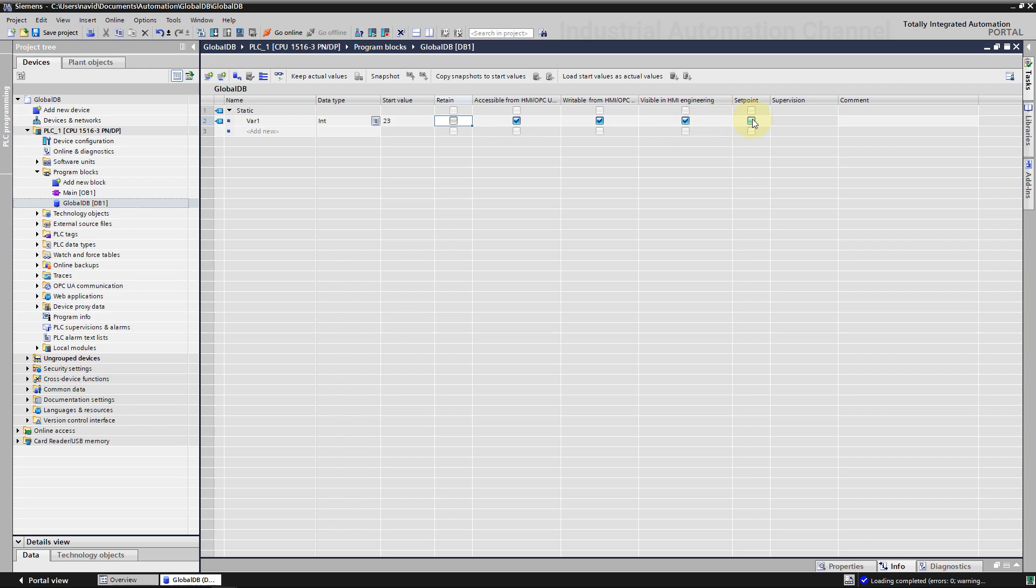Next, we can mark tags as set point. During commissioning, these tags can be initialized online and we don't need to set the CPU to stop mode. It can remain in run. In addition, the current tag values can be transferred as start values to the offline program and saved. When we run the program, I will show you how all these properties work. Define some other types of tags.